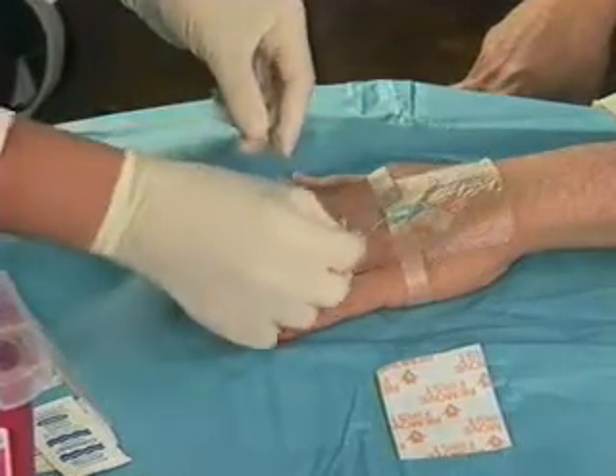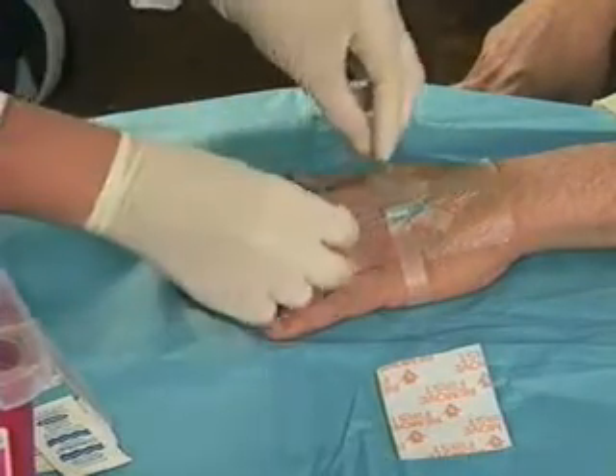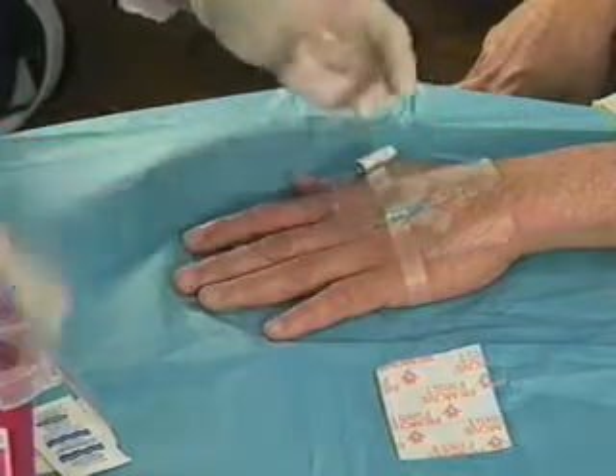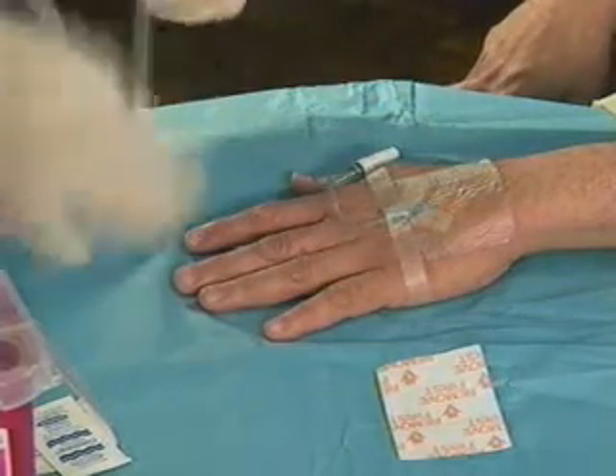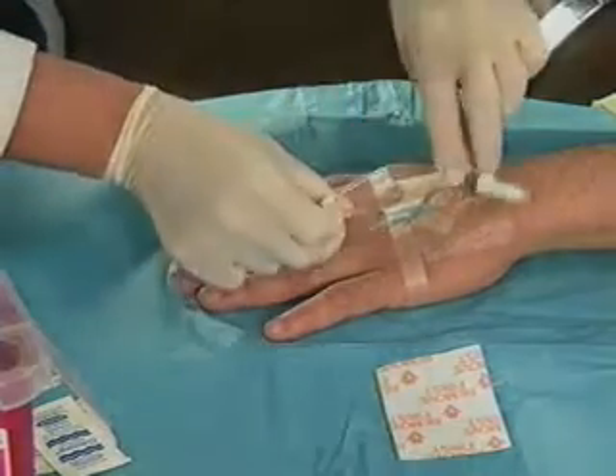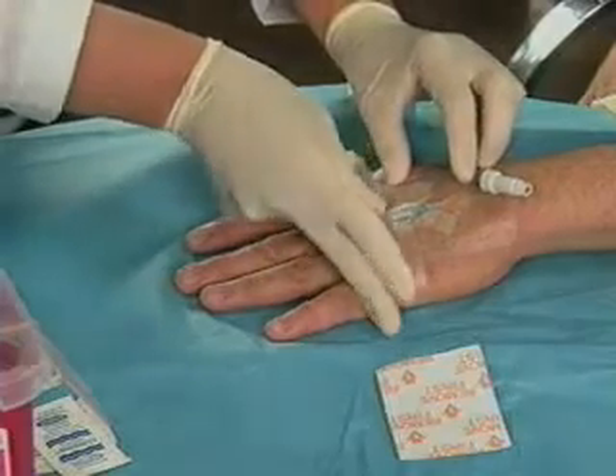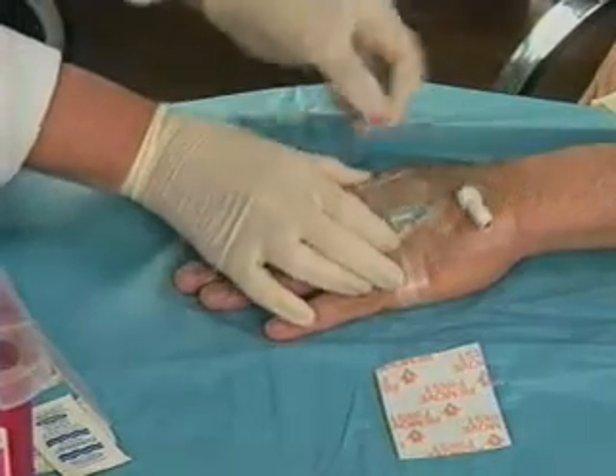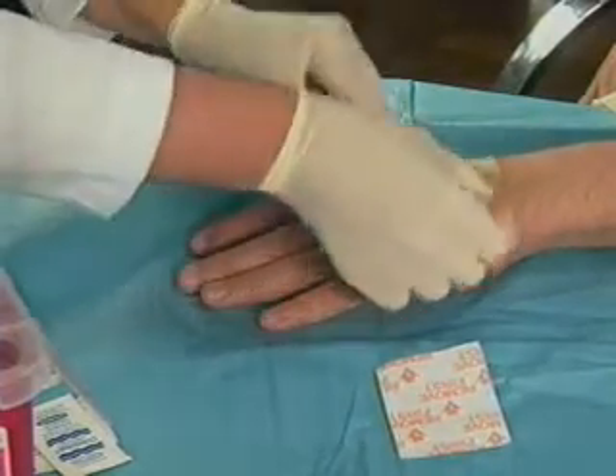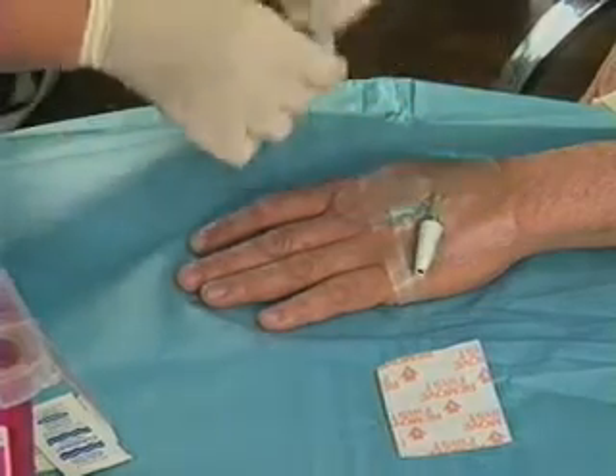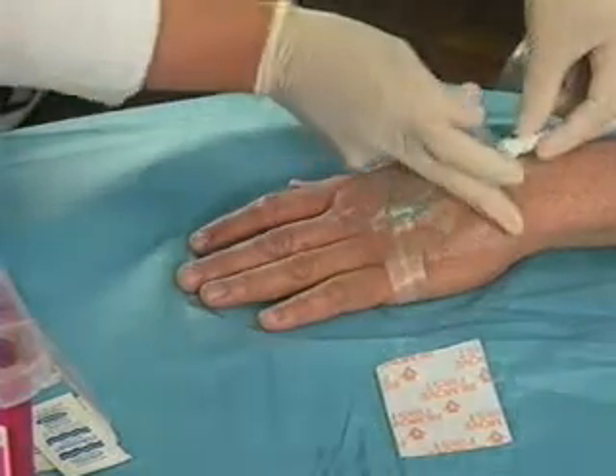The slide clamp can be maneuvered up and down the extension set, or it can be removed. Tape the tubing in place according to agency policy. Loop and secure the tubing with tape near the catheter tubing connection to prevent pull on the catheter.